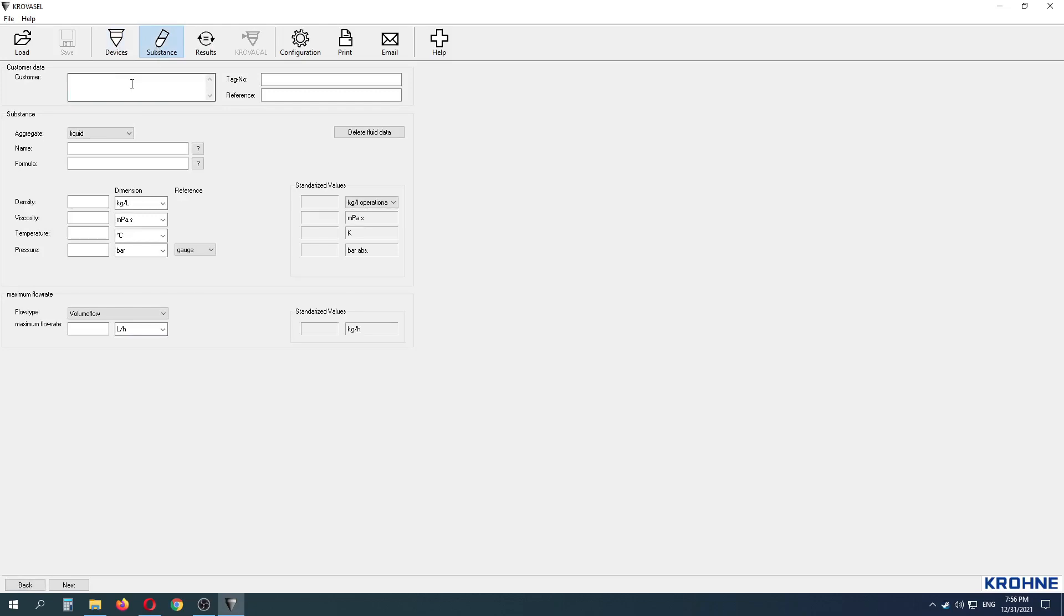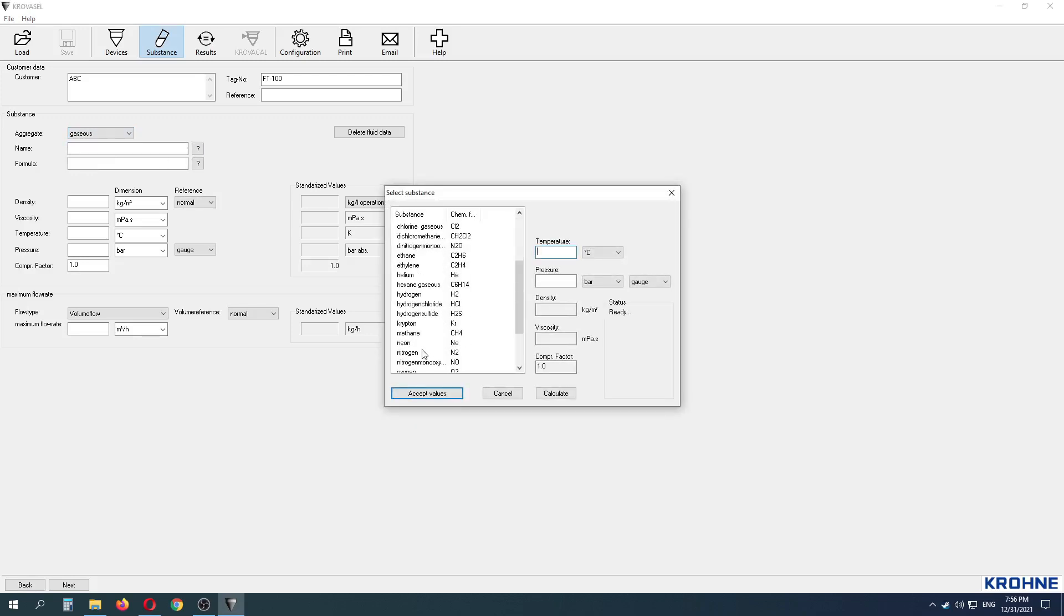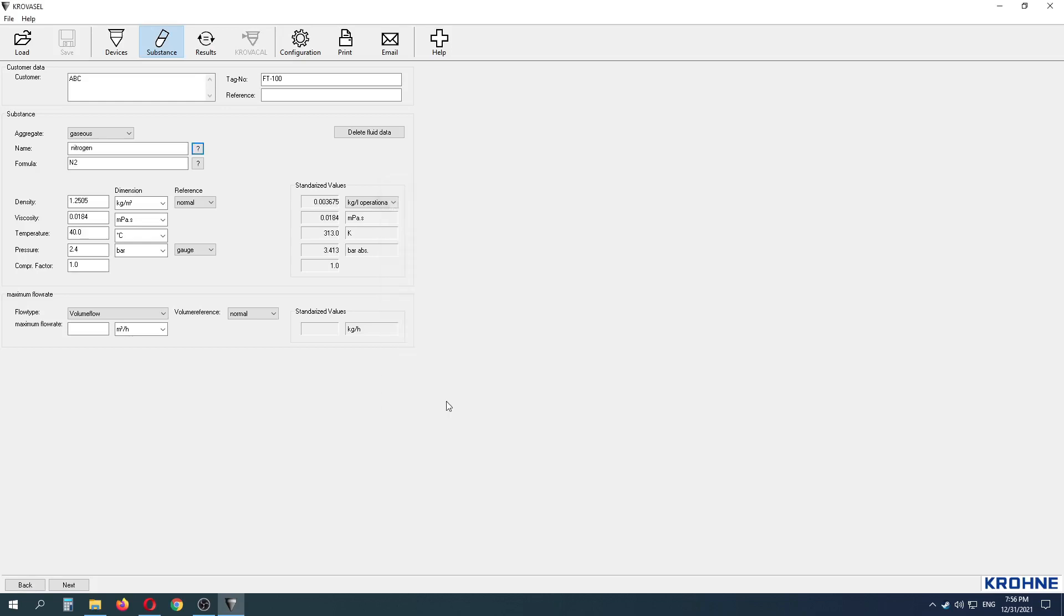At the Substance tab, we have to provide input data of process fluid. Nitrogen gas with temperature of 40 degrees Celsius and 2.4 bar G pressure considered here. Maximum flow rate shall be 40 Nm cube per hour.